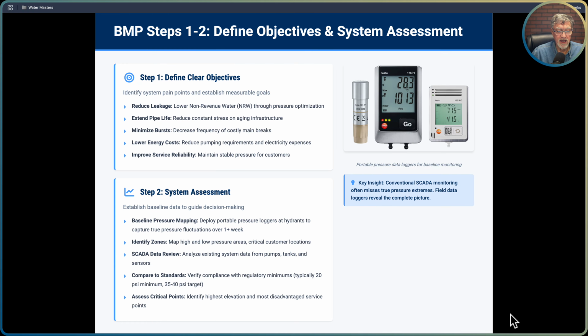So, SCADA data review: analyze existing system data from pumps, tanks, and sensors, and make sure that your SCADA is capable of handling internet connected sensors and PRV valves. That's going to be important. Is our SCADA up to the task? Compare to the standards, verify compliance with regulatory minimums. We want to make sure we maintain pressure according to our regulatory standards and assess our critical points. Identify the highest elevation and most disadvantaged service points and figure out how you're going to tackle that.